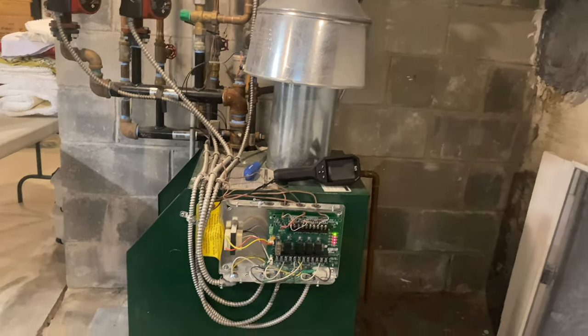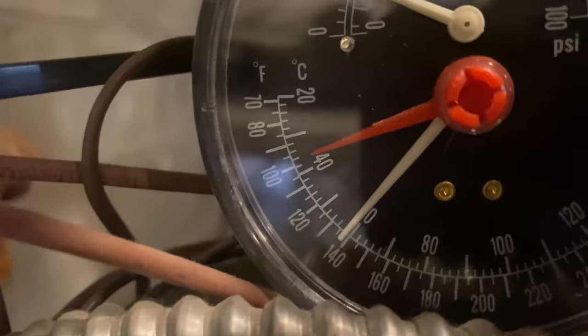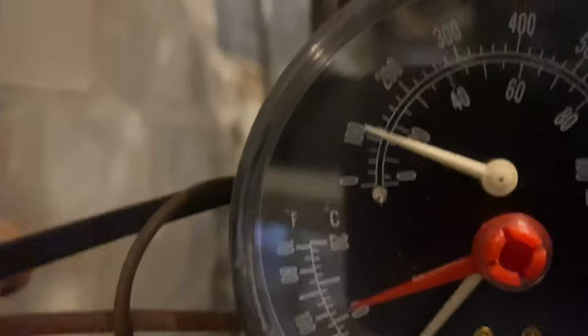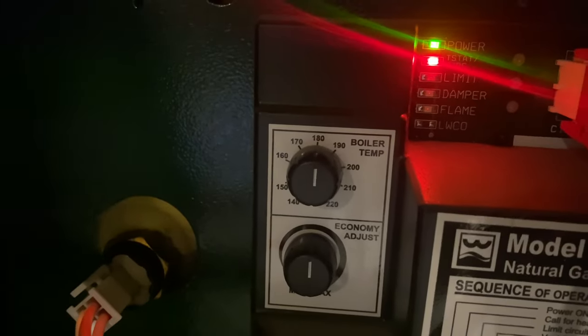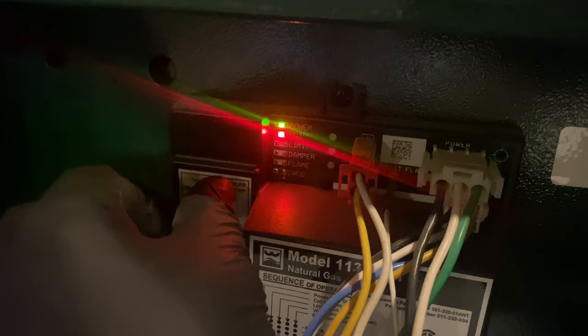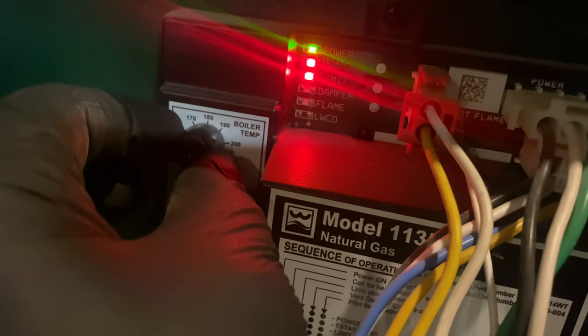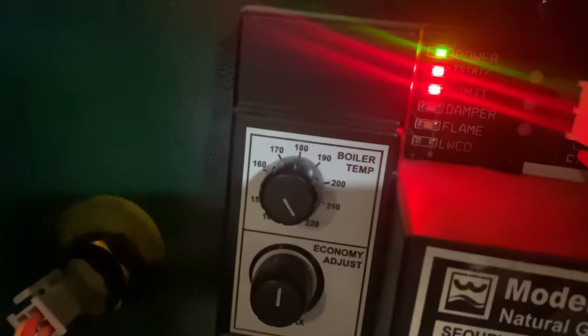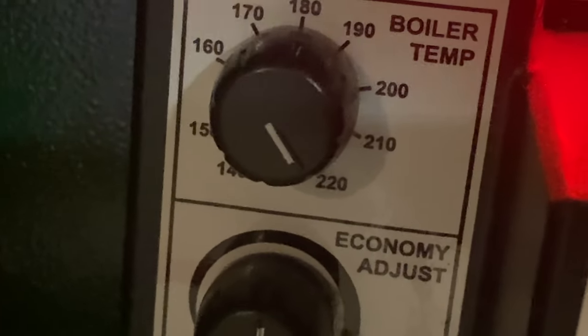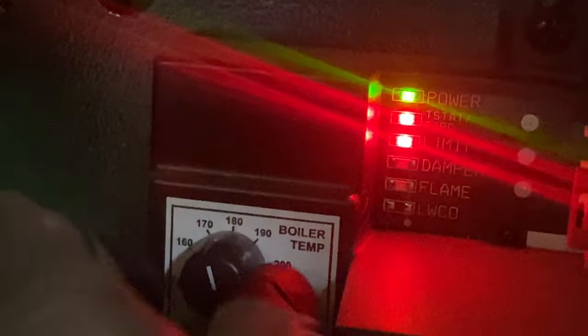Okay, so it just turned off again. Our temperature is 140, pressure's fine, a little under 20. But that's set for 180, and it turns off. If I crank this up, only when I go all the way up to 215 degrees did it actually do that. Now let's go back down. See, no change in that.